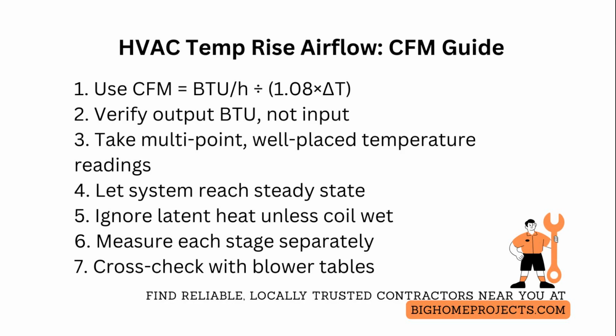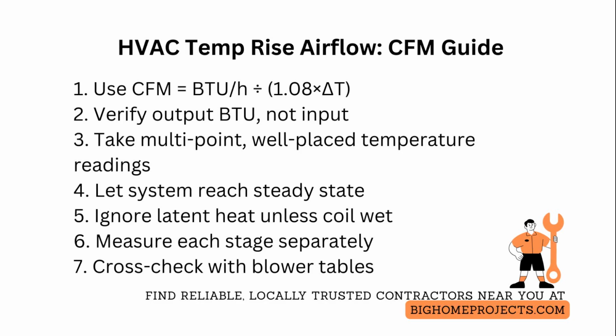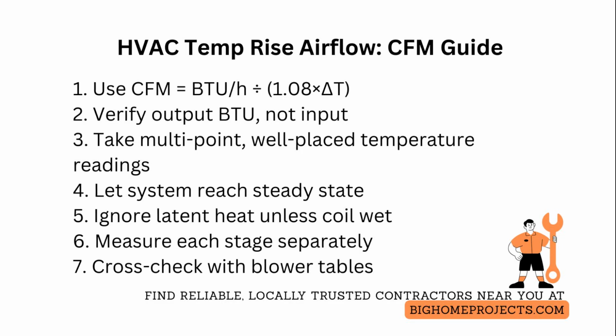Measure output British thermal units per hour from the rating plate, then adjust if the high fire input is clocked lower or higher than nameplate by multiplying by measured input to output efficiency, not the rated efficiency.